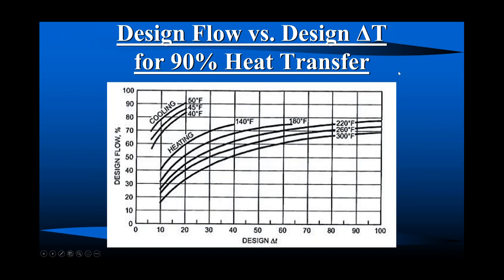So this is a chart, kind of a different chart, but it's relevant. Design flow versus design delta T. So we got design delta T at the bottom here, design flow on the left-hand side, and different supply water temperatures for cooling systems and heating systems. For 90% of heat transfer, we'll talk about that. So design flow versus design delta T for 90% of heat transfer. So where do we find this crazy chart? Well, it's in the ASHRAE handbook on testing and balancing. So let's take a look at what this chart tells us.